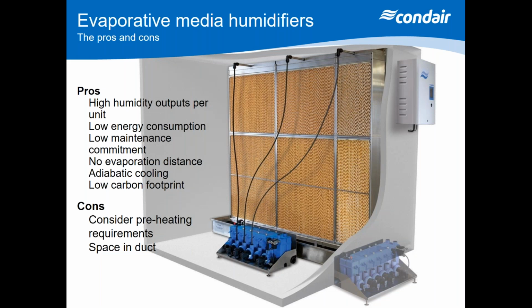In terms of the installation of these units, obviously they're going to be put into an application for humidification. It's very, very important to have the correct preheat onto these units, because the adiabatic process is cooling the air at the same time. If your preheat isn't sufficiently high in the winter, normally 30 degrees above, you're going to struggle to get the conditions in the room itself. So preheat is a requirement for these. You've got to have indirect gas heating to make the benefits of the energy savings there and to give you the control you want.